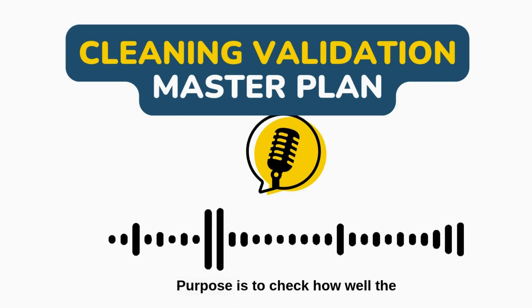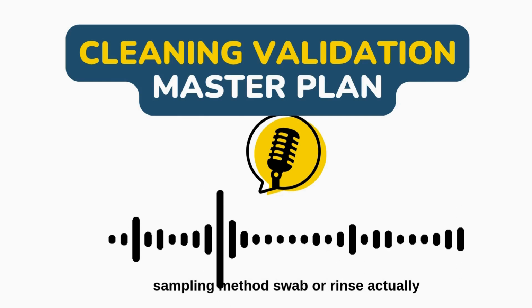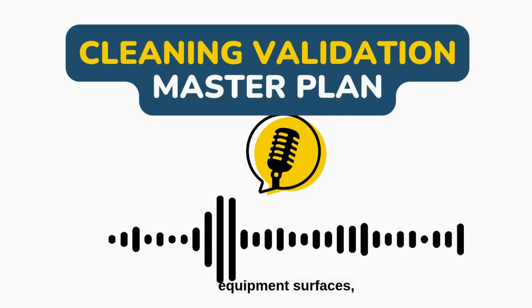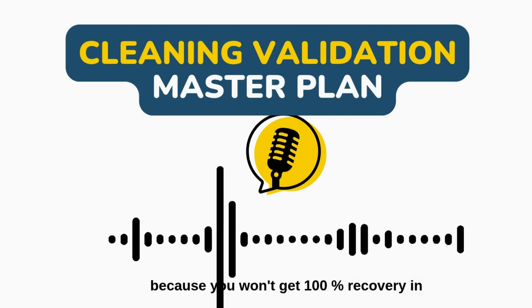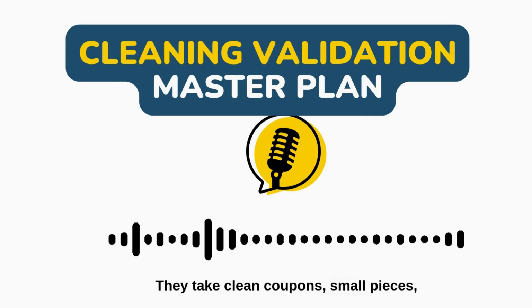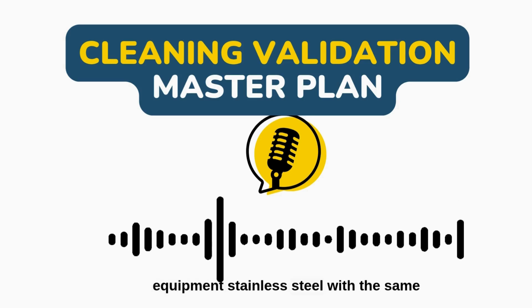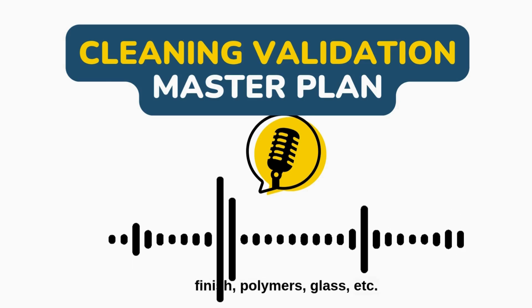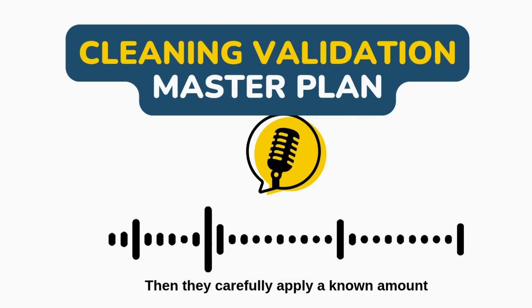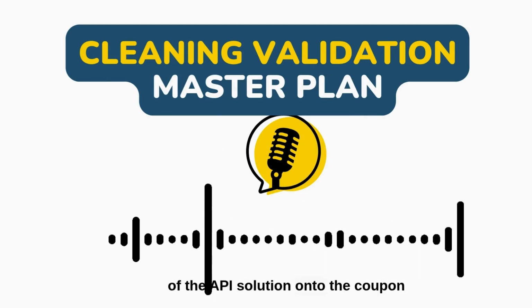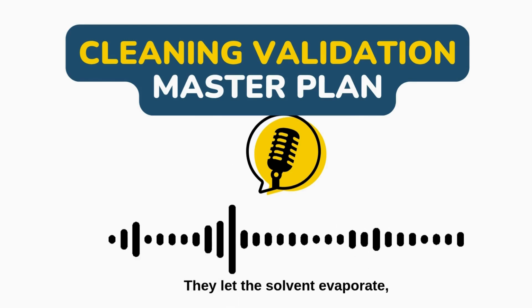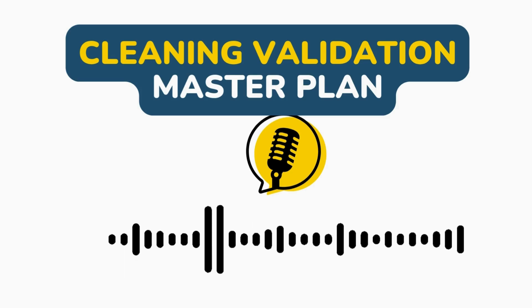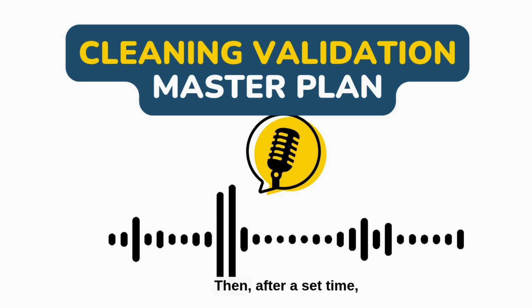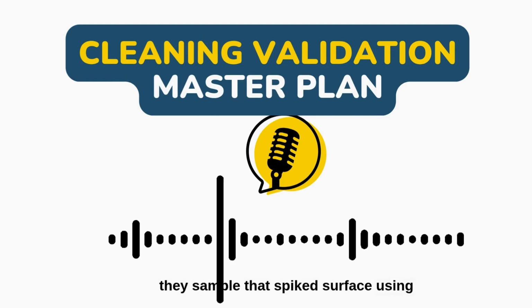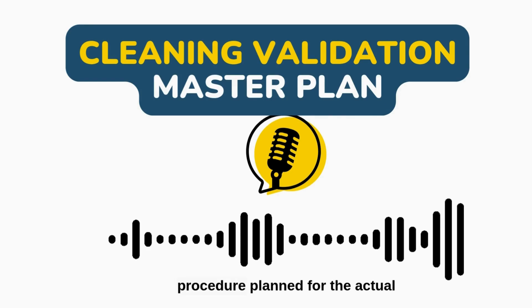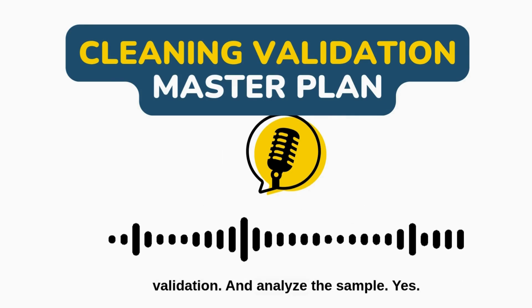They really are. The purpose is to check how well the sampling method, swab or rinse, actually recovers the residue from the specific equipment surfaces, because you won't get 100% recovery in reality. How do they do it? They take clean coupons, small pieces, of the actual materials used in the equipment: stainless steel with the same finish, polymers, glass, etc. Samples of the equipment surface. Yeah. Then they carefully apply a known amount of the API solution onto the coupon surface, that's the spike. They let the solvent evaporate, leaving a known residue amount, mimicking dried-on product. Exactly. Then, after a set time, they sample that spiked surface using the exact same swabbing or rinsing procedure planned for the actual validation. And analyze the sample. Yes.